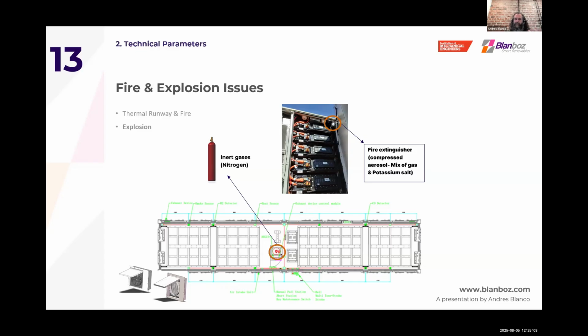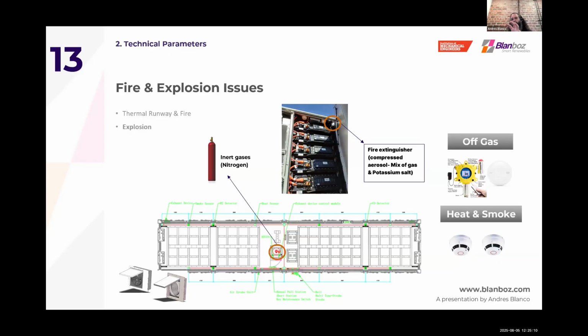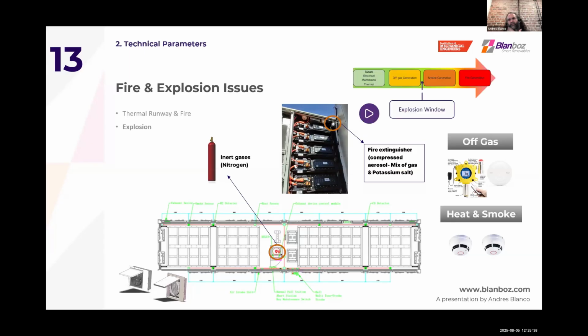These are not mandatory currently, depending on the local authority, but by guidance, they are not mandatory. And that's why, you remember when I mentioned the 13 minutes, the point when the cells start venting is very important, because here is when we can add sensors, combustible gas detectors, particularly hydrogen, because that's the highest concentration that you will get when the battery starts venting, that you can detect early enough to trigger any safety mechanism before the fire. So your explosion window is likely to happen through this off-gassing event, and this normally happens before smoke, when the cells are being burned, and before the fire.